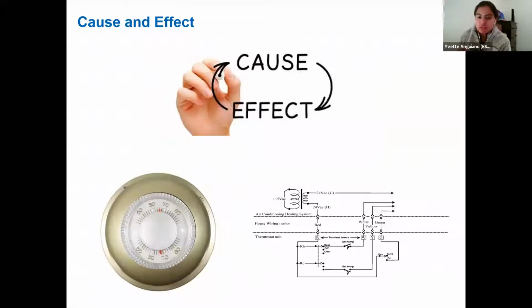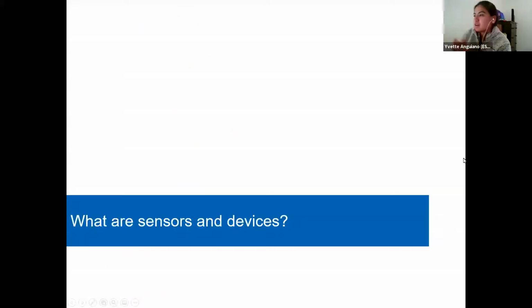And to go a little bit further into that, you want to go into the cause and effect, basically, is how you'll see what instrumentation is and why it's necessary. All of these instruments are reacting to changes in temperature, humidity, or other day-to-day changes. It all boils down to this cause and effect, like this simple thermostat. Whether there's a rise or fall in temperature in a space, you can have dampers open, fans turn on, and valves open for cooling and heating. And then when the space meets a set point, the system reacts and starts closing various dampers or valves, and turning off fans. So that was just a simple explanation of instrumentation. Then we can get further into the weeds of what are sensors and devices.